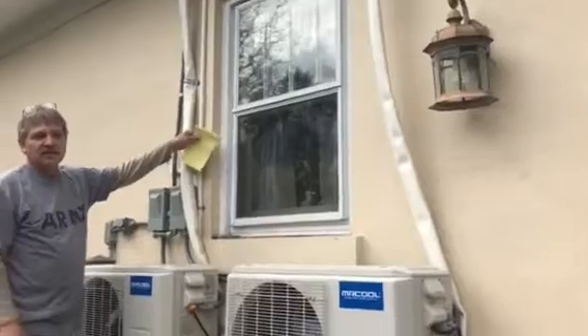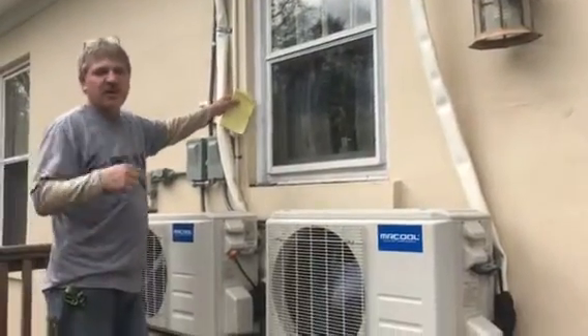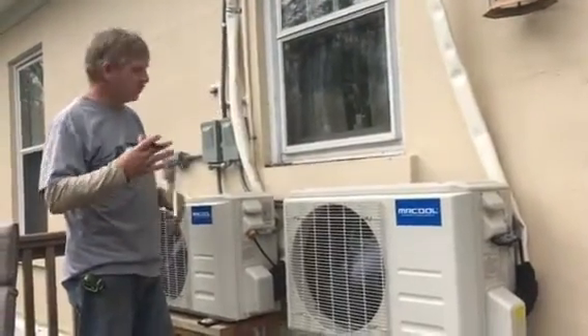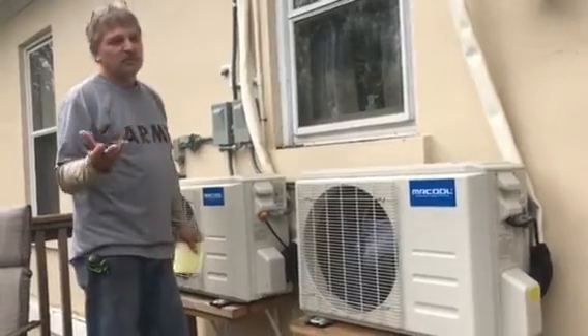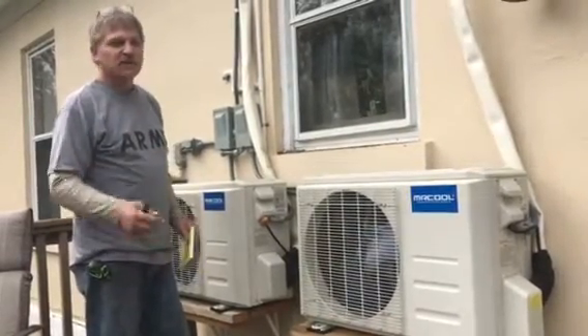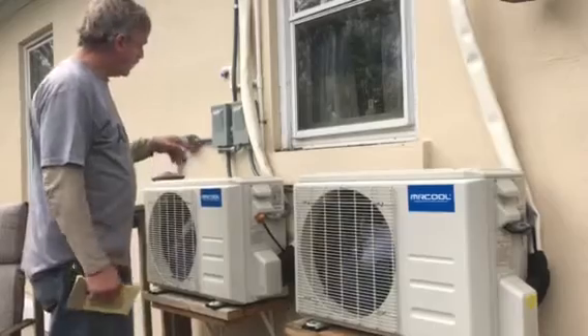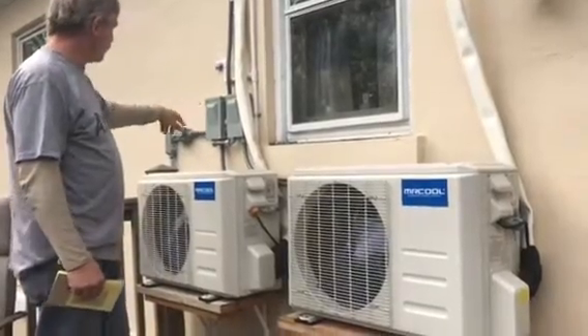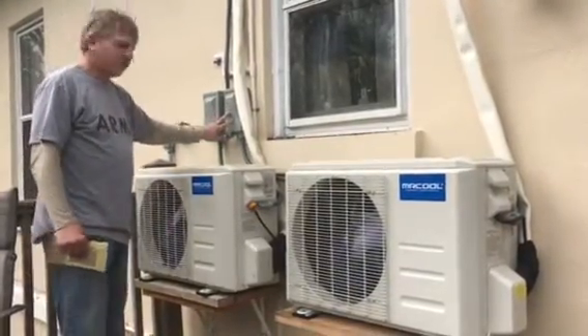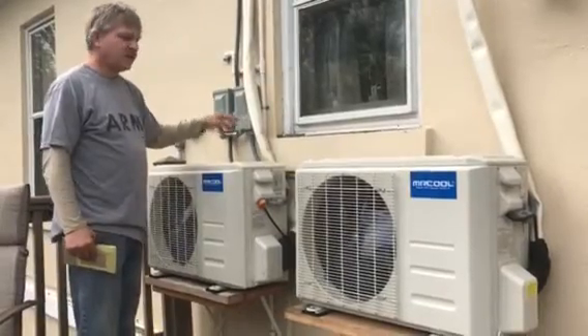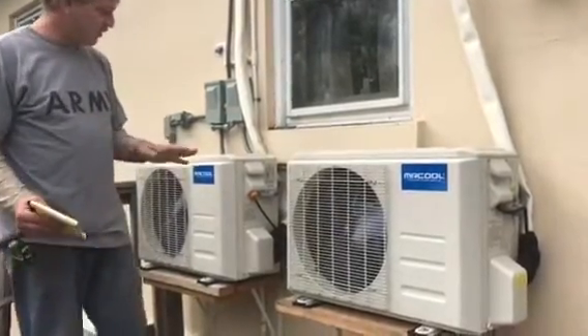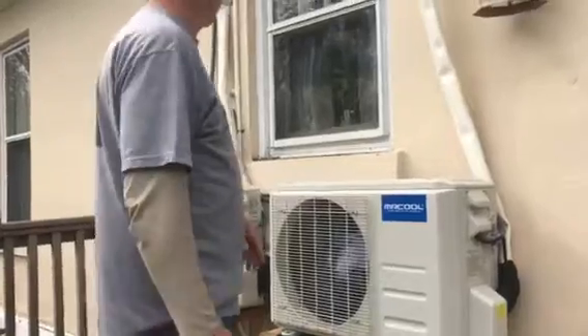sub panel or down to the circuit breaker box. These are your water lines that take care of all the condensation that's taken out of the room you're heating or cooling. Water comes out when you're cooling, but you still need drainage lines. These are your disconnect boxes. You've got to have a disconnect for each unit in case you ever need to work on them or do anything with them.